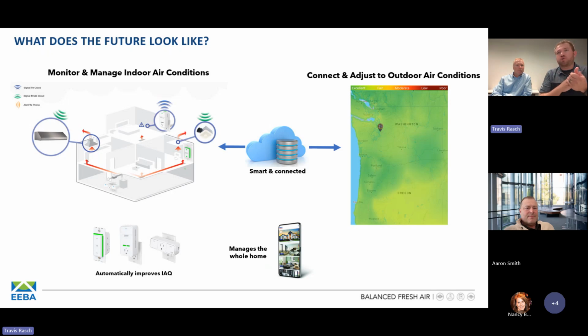We're not asking the homeowner to go and turn off something. We're going to use that outdoor data and make that decision. We've set our thresholds. When that reaches this threshold, it's not a good time to be bringing outdoor air in, so let's shut it down. Again, we're always going to be looking to see when we've gotten back to good outdoor air conditions, and then right, turn it back on, et cetera. So I think it's great.